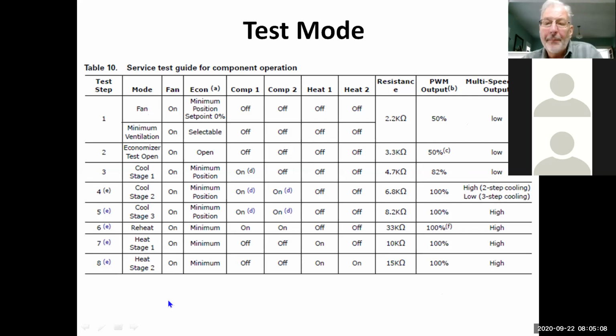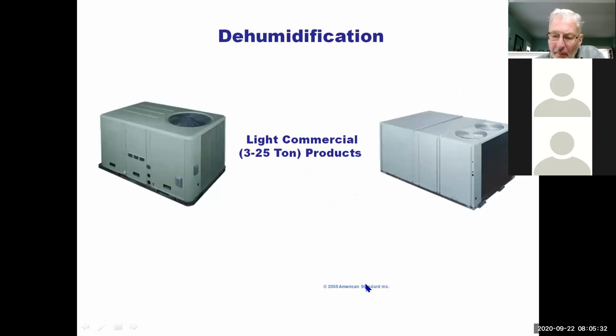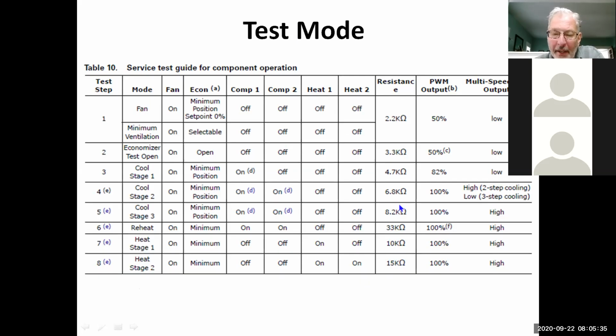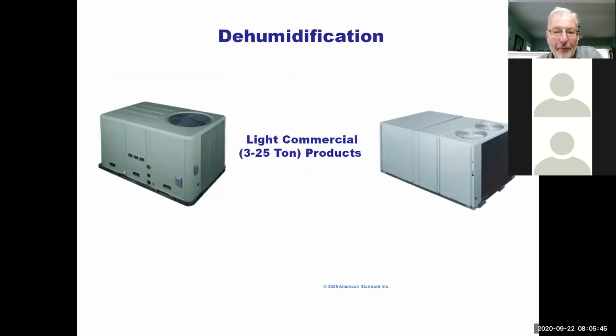Now there's another way to do it. If you have a decade box or a resistor, say you take an 8.2 k ohm resistor and put it on test 1 and test 2, it'll go directly to cooling stage 3. Or if you put a 15 k resistor on there, it'll go directly to heat stage 2. If you're doing maintenance and you want to carry a decade box, or a resistor to put on there, it will drive it there that much quicker. So, things to remember when you're in the field.